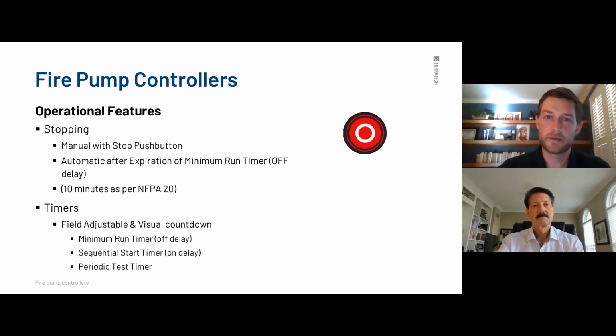And the reason that we ship it that way from the factory is that an automatic stop per NFPA 20 again is required to be signed off by an AHJ. So we don't presume that the AHJ in every market will appreciate an automatic stop. So we send it in the field as manual. And if the AHJ wants to sign off on that, then it can easily be field enabled to be automatic, stopping after 10 minutes.